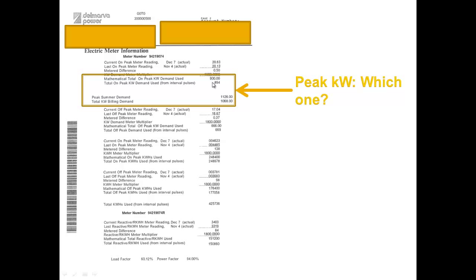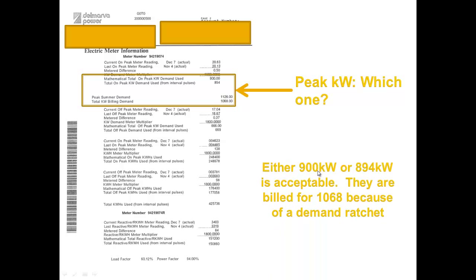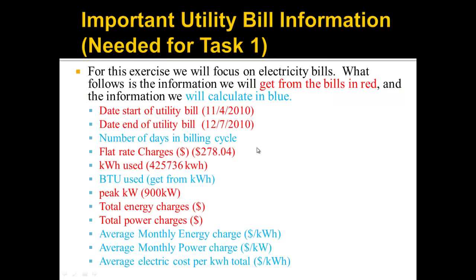Either one of these — the 900 or the 894 — I would accept. The big difference that's notable here is there's a ratchet, because we have the peak summer demand, which is 1,126 kilowatts, and what we're actually charged for is a percentage of that peak billing demand, which is 1,068. What I want is the 900 or 894 — the actual peak of that month. I do not want the peak summer demand or the total kilowatt billing demand. That's something to note when doing your analysis. We'll put 900 kilowatts in the table.